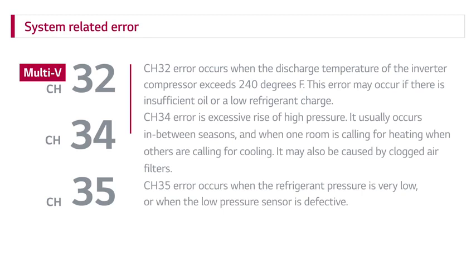CH-34 error is an excessive rise of high pressure. This error usually occurs in between seasons when one room is calling for heating while all the others are calling for cooling. CH-34 may also be caused by clogged indoor air filters.